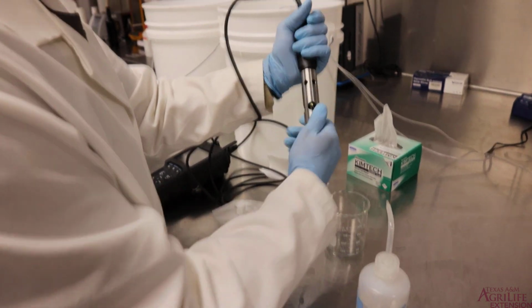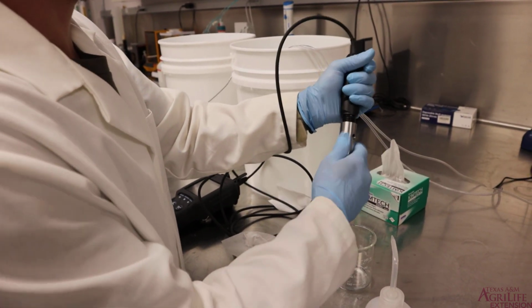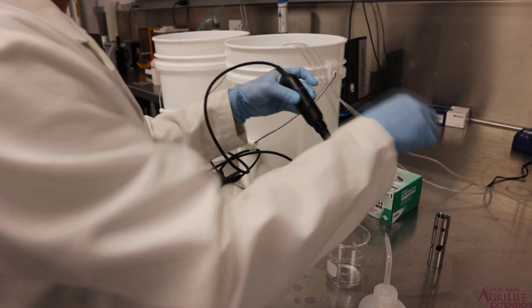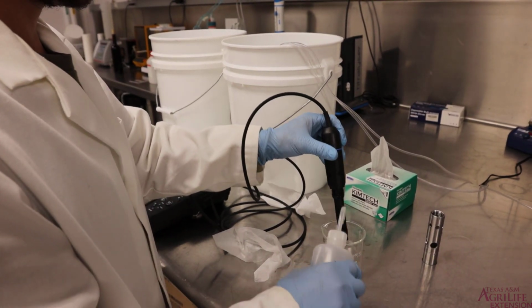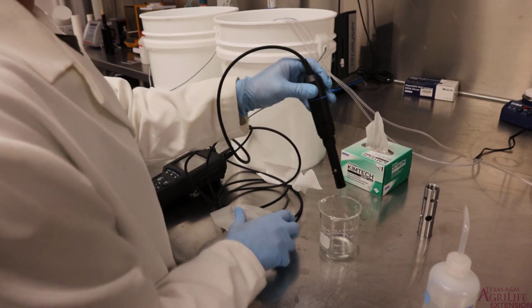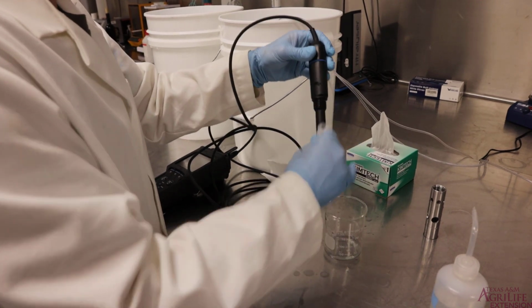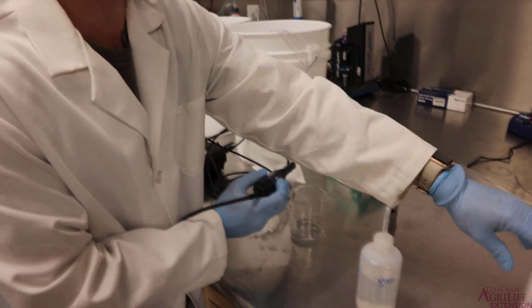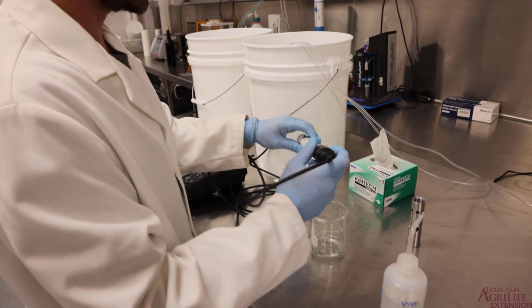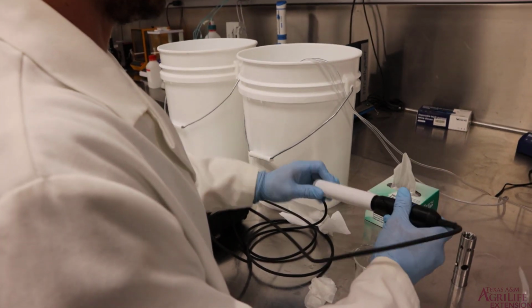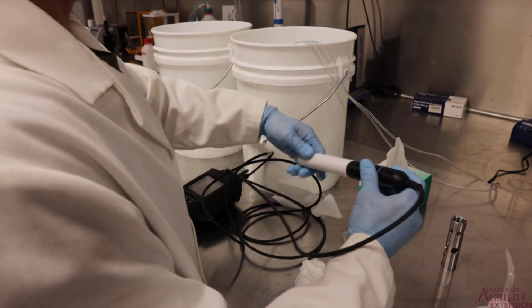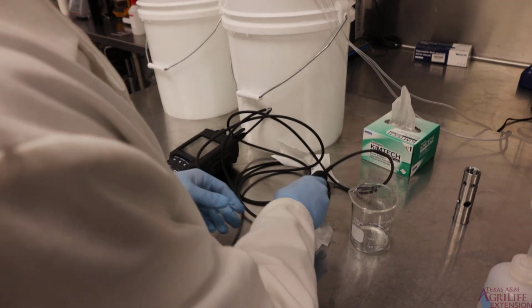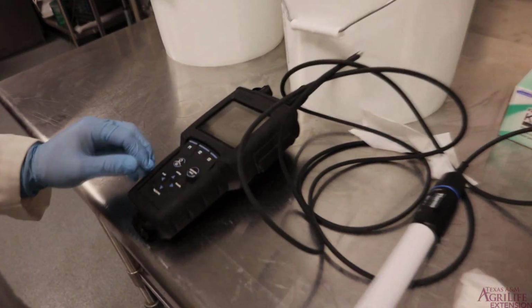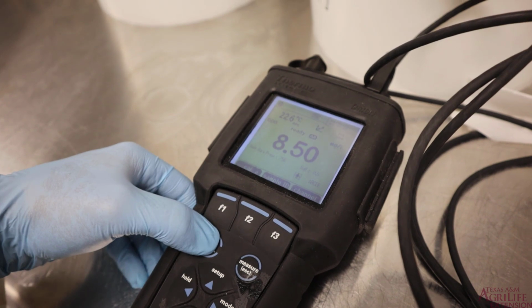We'll remove our metal protective casing. We'll give our probe a wipe and a little spray with some DI water. We'll wipe it down, and since we're finished with our analysis, we will grab our white casing and put it back on. Once we're done with that, we can go ahead and hit the power button on the DO probe, same way we turned it on, and power it down.